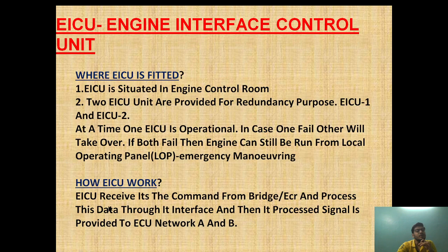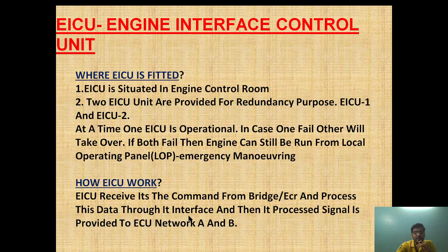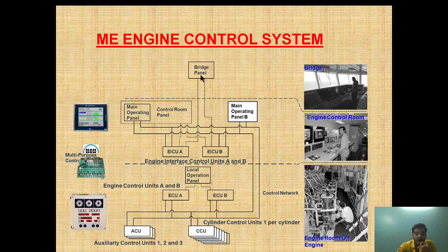What is EICU doing? EICU receives its command from the bridge or the ECR. If control is on the bridge, the command comes from the bridge, is processed to the MOP panel, then goes to the EICU. The EICU processes this data through its interface, and the processed signal is provided to ECU network A and B. So if someone asks you the function of EICU, you should say: EICU processes the data given from the bridge and after processing, converts it into a signal and gives it to ECU network A and ECU network B.